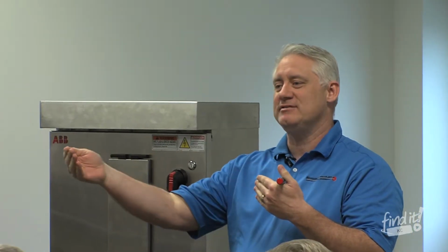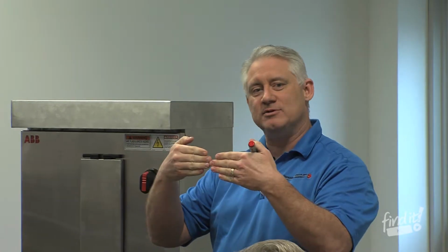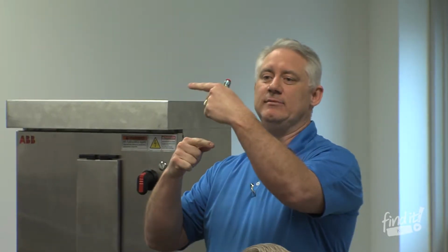We can get reflections of that 650 volts back towards the drive. And when the 650 volts meet in the middle, they essentially can double. And because of some of the overshoot issues, they could actually more than double. We won't get into that unless you guys want to dig deeper. But a 1600 peak volt motor is going to protect you for some pretty significant distances. And it's going to allow your motor to live longer. And most motor manufacturers today, their standard windings are rated for 1600 peak volts.